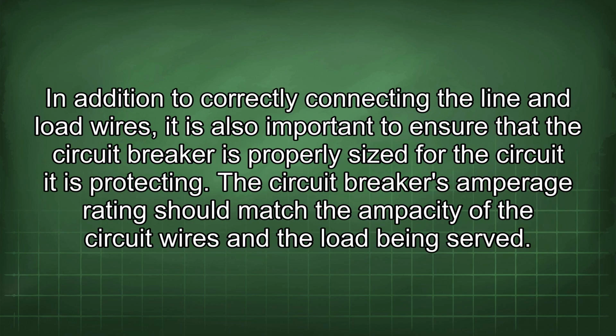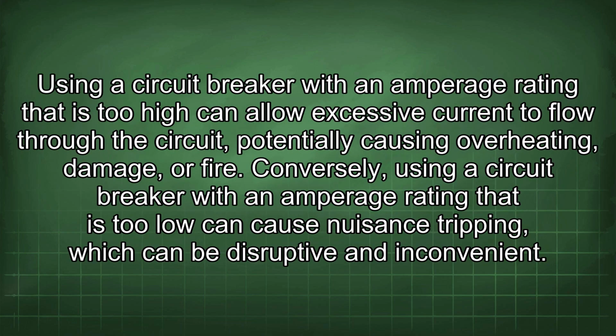In addition to correctly connecting the line and load wires, it is also important to ensure that the circuit breaker is properly sized for the circuit it is protecting. The circuit breaker's amperage rating should match the ampacity of the circuit wires and the load being served. Using a circuit breaker with an amperage rating that is too high can allow excessive current to flow through the circuit, potentially causing overheating, damage, or fire.